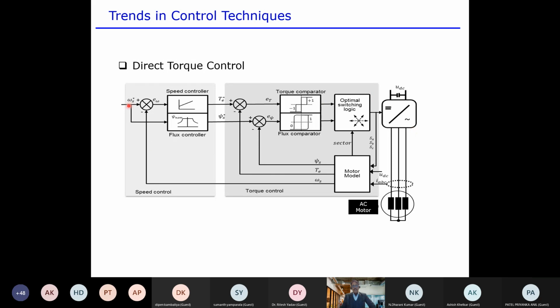What is the difference between vector control and direct control here? There is a speed controller loop, and a speed dependent flux controller loop. There is reference flux and actual flux, reference torque and actual torque, fed to torque comparator and flux comparator. Output of these comparators is fed into the optimal switching logic or optimal voltage vector generator. Instead of a PWM signal, we directly feed which switch should be on or off among these 3 legs. That command is fed to the inverter, giving faster control of the motor.